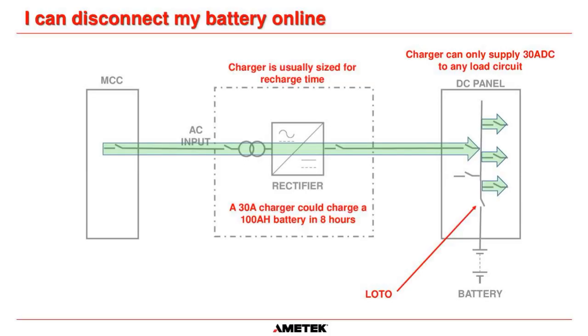That's not my goal. So John says, but it needs to be able to recharge the battery from full current and still feed the panel loads. So yes, you are correct. So let's say, going back to John's question about how should you rate the charger. Okay, let's say the design engineer has come up and said, okay, every load that we're ever going to have is 100 amps on this panel here.